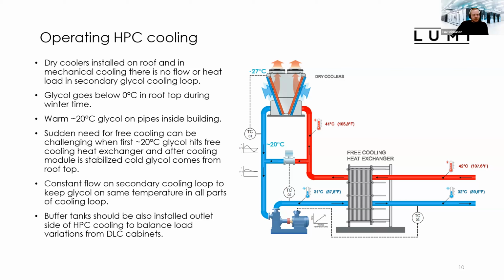So this is something that should be thought about more in the design phase, to have some kind of side flow, constant flow, also in this glycol loop to maintain stable temperatures in all parts of the cooling loop. And also buffer tanks should be installed on the outlet side of the HPC cooling to balance load variation from the directly cooled cabinet.